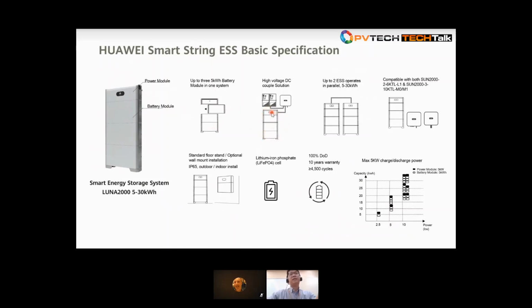Now, Huawei's Smart ESS is compatible with both Huawei's single-phase and 3-phase inverters. As we know, the DC voltage for single-phase and 3-phase is different. For the single-phase inverter system, the DC operating voltage is normally at 360 volt. It's a range between 300 to maybe 500. But for the 3-phase, the DC voltage will be even higher, between 800 volt to 1000 volt. So with Huawei's power module, we can adjust this high voltage and convert it into 48 volt and charge the battery module. That is the function of the power module. It will adjust to different systems automatically.